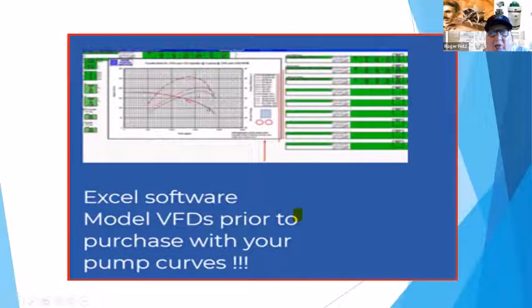So I know over time this is becoming more and more informative and helpful, because the power companies had gotten burned a little bit about the energy savings of drive controls on irrigation. They found out, well, gosh, we put this on, but they forgot to take into consideration the amount of acre feet. It was pumping 1,000 gallons a minute before at full speed, and then we backed it down to 600 gallons. Well, they still need to get that 1,000 gallons to those crops over a certain period of time. So it wasn't true savings. Plus you had losses in the VFDs and things.